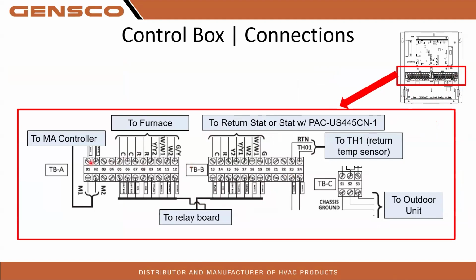If you have a wired Mitsubishi controller, this right here, pins 1 and 2, says M1, M2 on it. That's where your Mitsubishi wired controller is going to land. Everything else on this TBA block is for your furnace 24-volt wiring. It gives you 2 reds and 2 commons. It doesn't matter which one you use. They just give you extras there for accessories and what you may need. As long as you have at least one of those connected up, you're fine. You don't need to do any jumpers between reds and commons or anything like that.